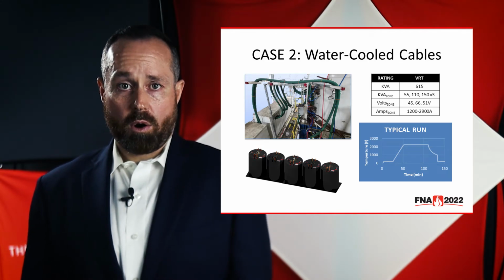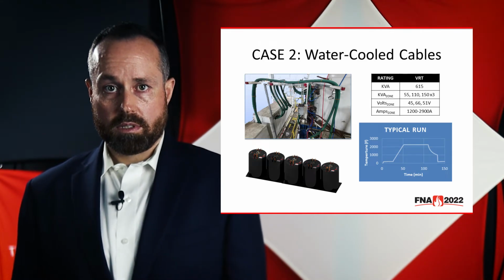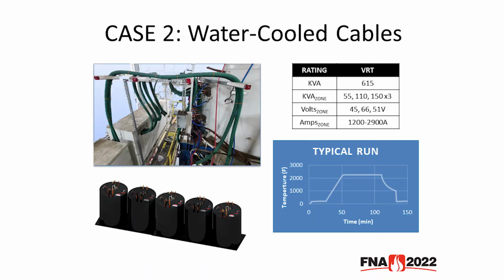Case 2 looks at the power impact of water-cooled cables. This is a 5-zone furnace rated at 615 kVA. The furnace has 3 side zones at 150 kVA, 1 top zone at 55 kVA, and 1 bottom zone at 110 kVA. A typical run was performed, shown here, and the power quality was assessed in only the heating circuit. The cycle consisted of a ramp up to and hold at 2200 degrees Fahrenheit. The run was satisfactorily completed without any issues.